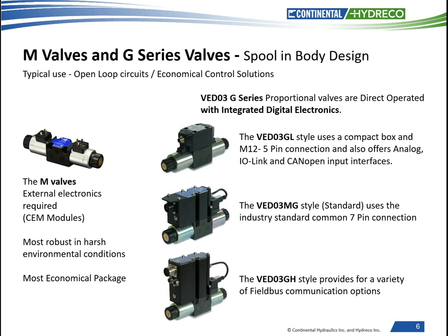The advantages of OBE: no panel space is required to mount a separate module to control the valve. Plug and play, or plug in and go. This means that they are factory pre-programmed to optimal performance and repeatable performance to the catalog specification. This gives you valve-to-valve interchangeability.